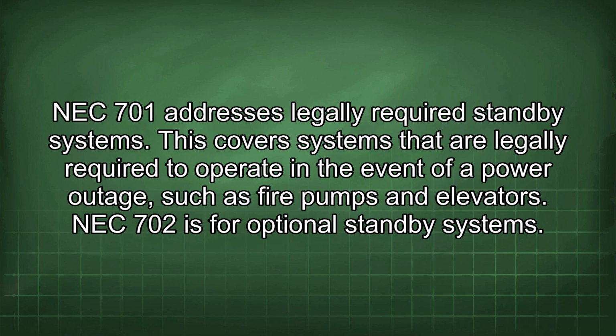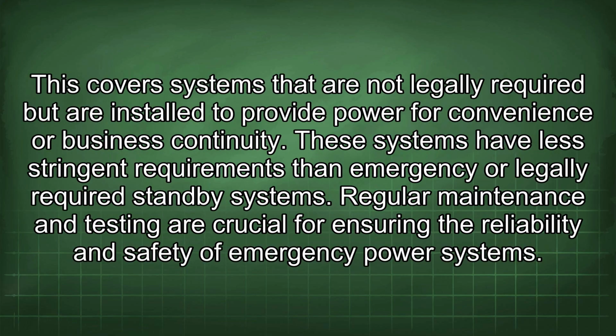NEC 701 addresses legally required standby systems. This covers systems that are legally required to operate in the event of a power outage, such as fire pumps and elevators. NEC 702 is for optional standby systems. This covers systems that are not legally required but are installed to provide power for convenience or business continuity. These systems have less stringent requirements than emergency or legally required standby systems.